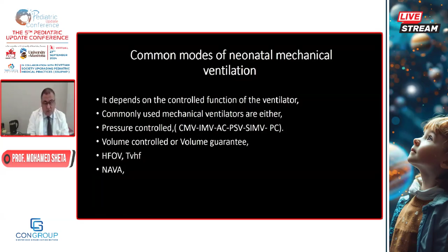There is a trigger, either by the flow of air to the baby when the baby starts to take a breath, or after the trigger, the machine will start to give the PIP, which will take almost 0.02 up to 0.1 seconds to reach the pressure limit set on the machine. Then comes the plateau, which is the inspiratory time, usually 0.3 or 0.4 seconds, depending on the condition, and then expiration starts, as you can see in our curves, for both airway pressure and volume.